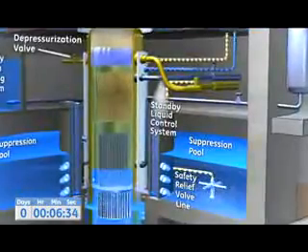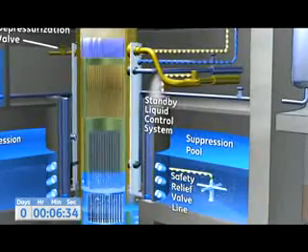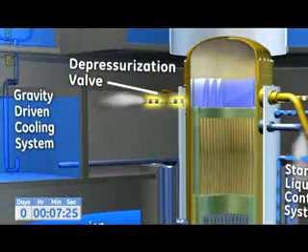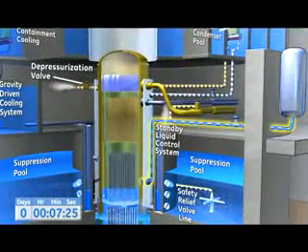This relieves pressure in the reactor pressure vessel. The depressurization valves open next, transferring steam from the reactor directly into the containment. At the same time, high pressure tank valves open, forcing liquid through piping directly into the core.